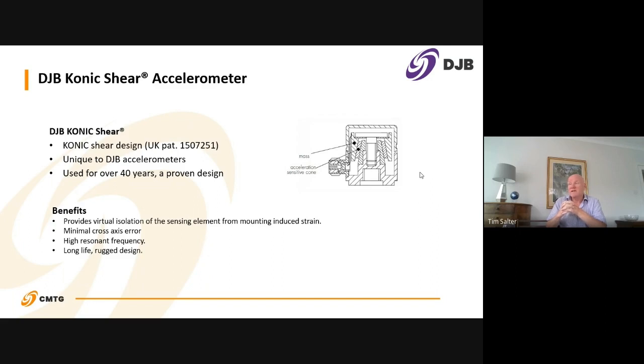Minimal cross-axis error. So cross-axis is the error that's induced by sideways vibration, if that's the right word to use, when you really want to be measuring only the acceleration in the vertical direction. If there's any horizontal vibration, that should be rejected, and Konic Shear is exceptionally good at doing that. Has a high resonant frequency, which is always important in an accelerometer, particularly during shock testing, and has a very, very rugged design. They do last a long time.